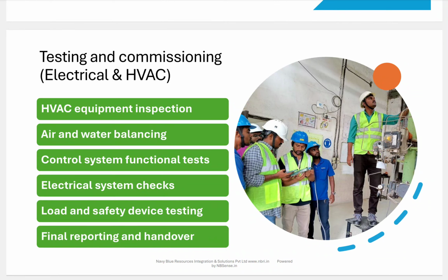Whichever the new project, retrofitted project, or any existing or new building, this testing we have to do, generally called third party testing commissioning. All electrical systems from the main incomer to the end usage point, all switch gears, systems, components, everything we check to make sure they perform as per expectation or design standards. Whereas the HVAC, heat ventilation and air conditioning system, again the high side, low side, all necessary and auxiliary components we test, making sure they work properly and perform their functionality or duty. That comes under testing commissioning.